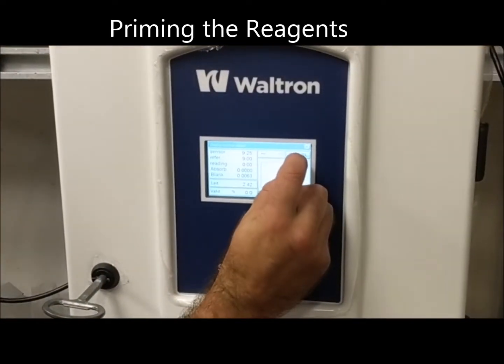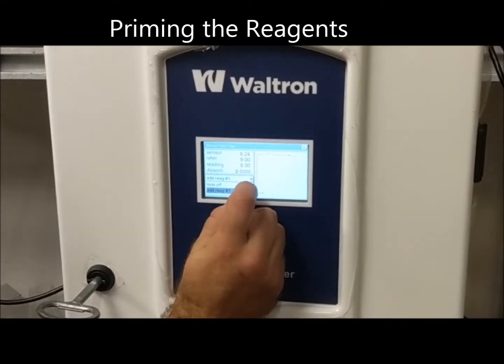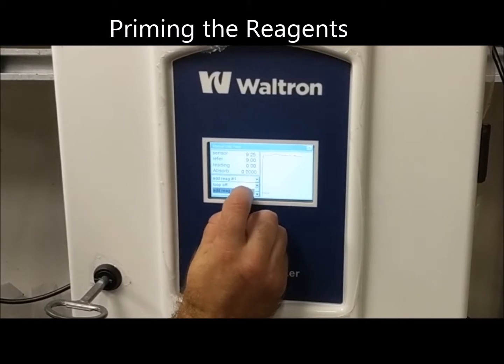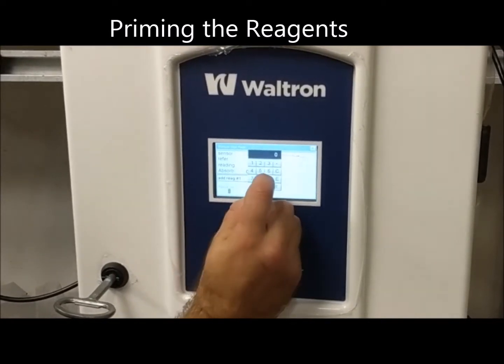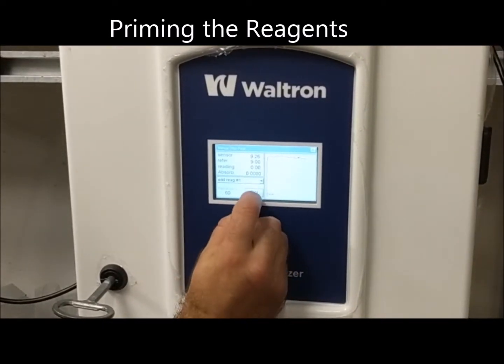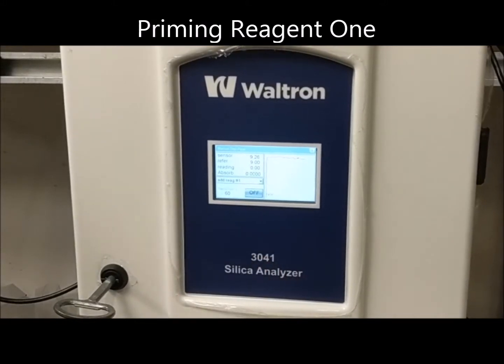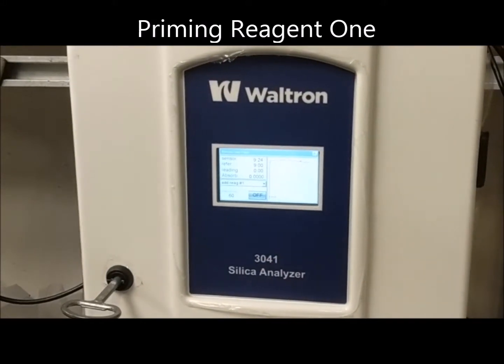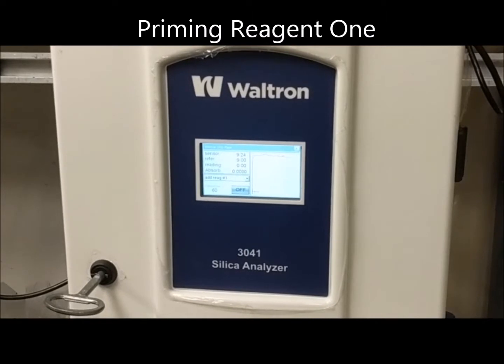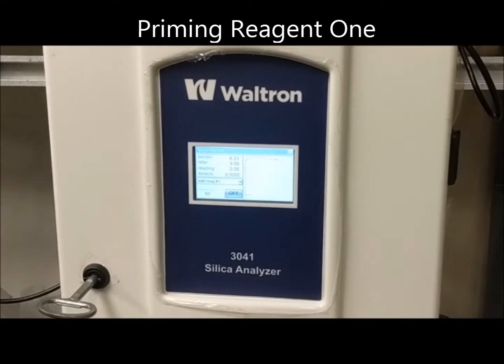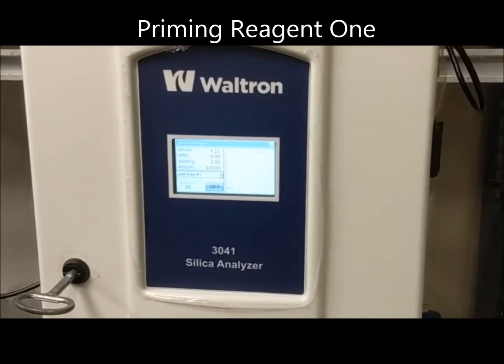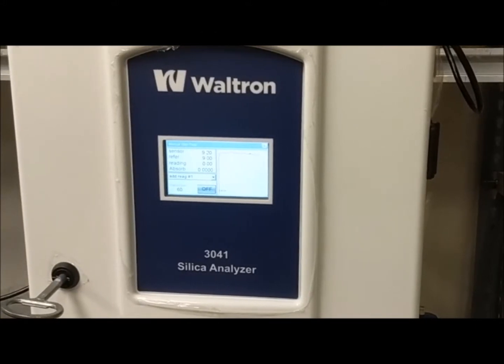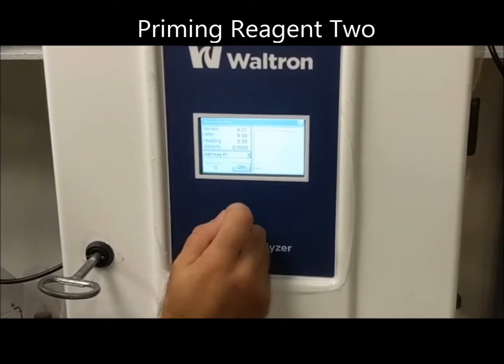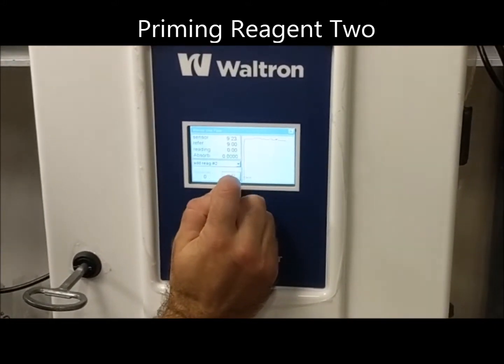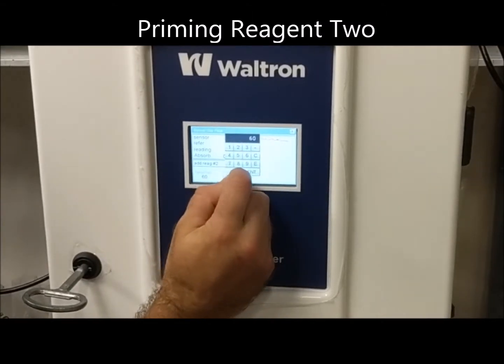In order to do that, hit the display button, press the manual button, scroll down through your list of commands to find add reagent 1, change your timing to 60 seconds, press the on button. You hear the reagent pump adding reagent 1, and after 60 seconds, the reagent line will be primed. After reagent 1 has completed, we will scroll through and do the same thing for reagent number 2, also 60 seconds.